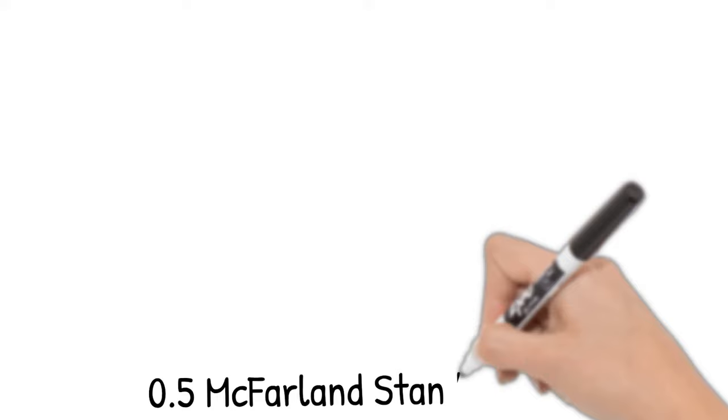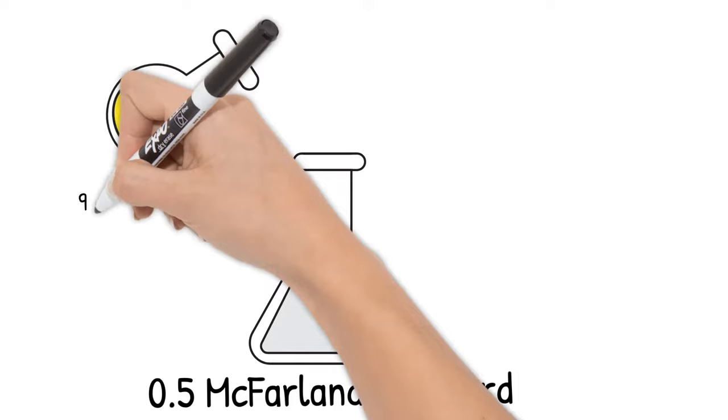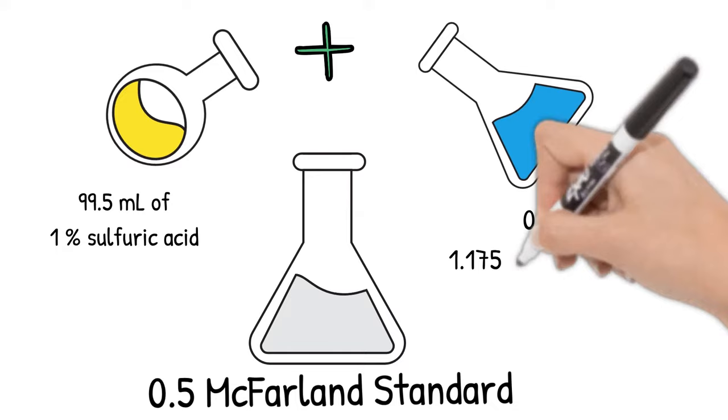How to prepare McFarland turbidity standards? The most commonly used is the 0.5 McFarland standard, which contains 99.5 ml of 1% sulfuric acid and 0.5 ml of 1.175% barium chloride.